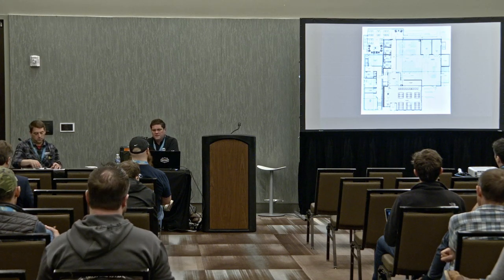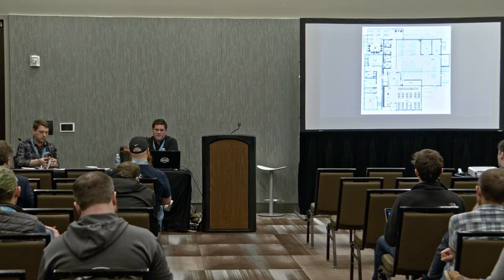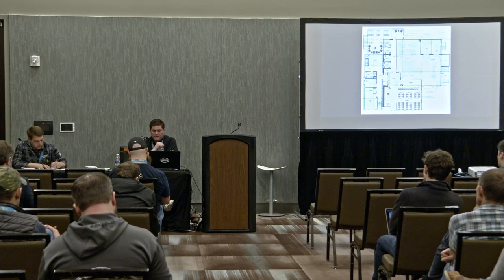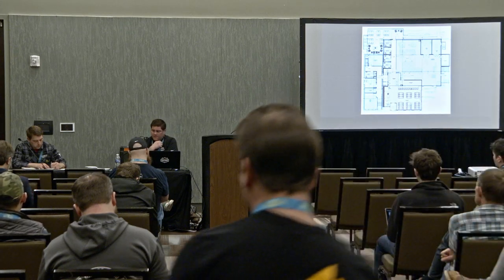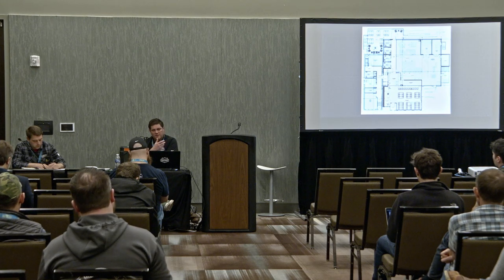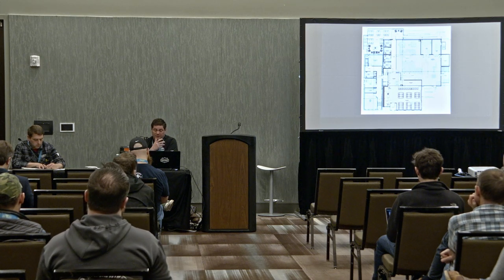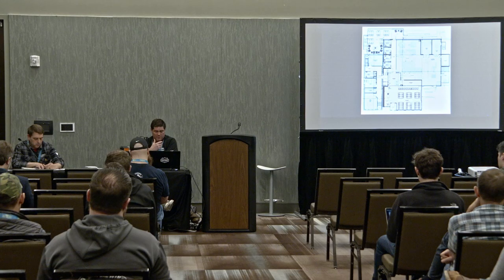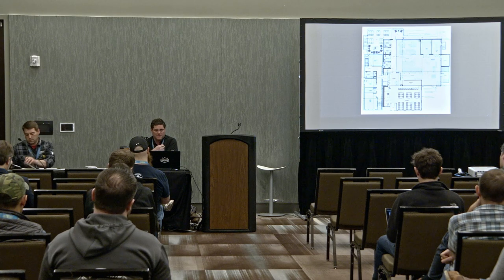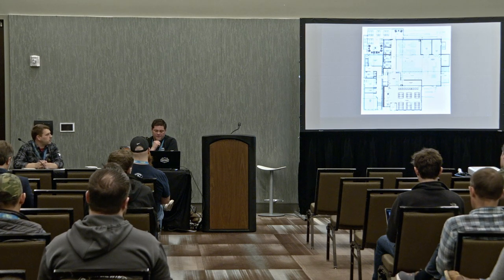There are a couple good companies that make electric steam boilers. Sussman is one of them. So if you don't want to pay these huge infrastructure costs of running longer steam lines for your brew house from a boiler room that could be 20 plus feet away, a Sussman boiler has a footprint that's half the size of this table, and they can be right next to your brew house. Above a 10 barrel is pretty tough. You'd have to have multiple in series, and it's a large draw on electric when your equipment's cycling.